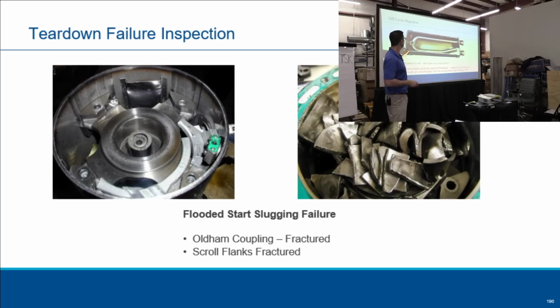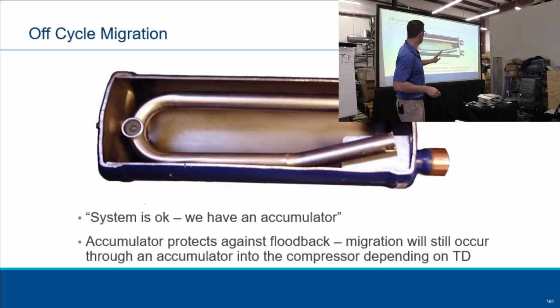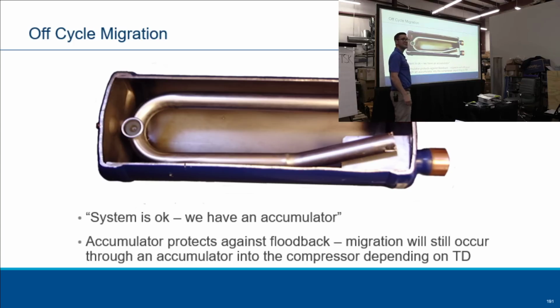System's okay, we have an accumulator. Is it okay for flooded starts? So what does an accumulator protect against? How about that? Flood back, right? So it'll make sure that you don't get refrigerant in the compressor. Does it protect against flooded starts? No. If that compressor for some reason is colder than that accumulator, what's going to happen is that here's your liquid refrigerant. All of a sudden it's going to go into your pipe, migrate back to your compressor, right? If that compressor is colder.